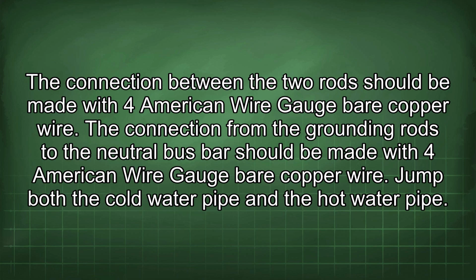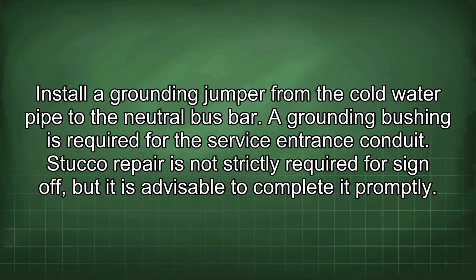The connection from the grounding rods to the neutral bus bar should be made with 4 American wire gauge bare copper wire. Jump both the cold water pipe and the hot water pipe. Install a grounding jumper from the cold water pipe to the neutral bus bar. A grounding bushing is required for the service entrance conduit.